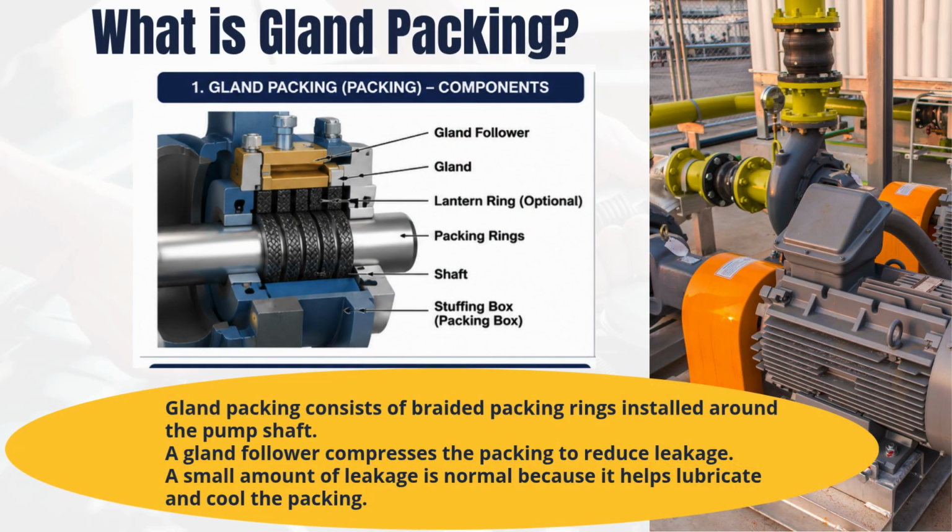Gland packing consists of braided packing rings installed around the pump shaft. A gland follower compresses the packing to reduce leakage. A small amount of leakage is normal because it helps lubricate and cool the packing.